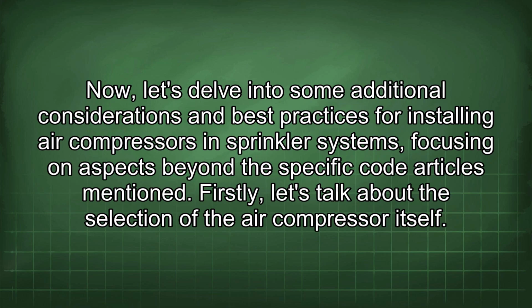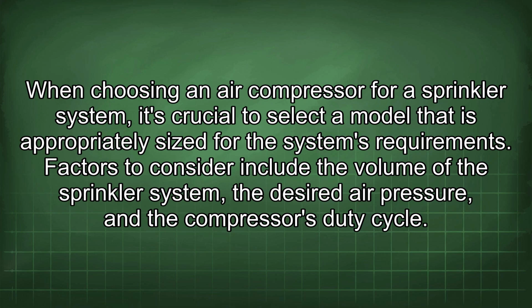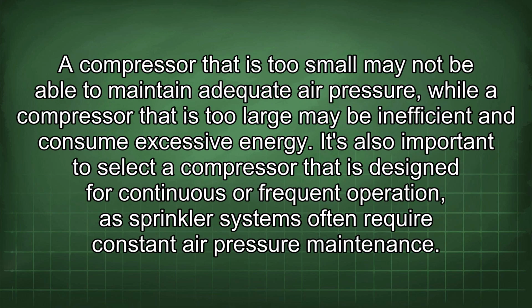Now, let's delve into some additional considerations and best practices for installing air compressors in sprinkler systems, focusing on aspects beyond the specific code articles mentioned. Firstly, let's talk about the selection of the air compressor itself. When choosing an air compressor for a sprinkler system, it's crucial to select a model that is appropriately sized for the system's requirements. Factors to consider include the volume of the sprinkler system, the desired air pressure, and the compressor's duty cycle. A compressor that is too small may not be able to maintain adequate air pressure, while a compressor that is too large may be inefficient and consume excessive energy.